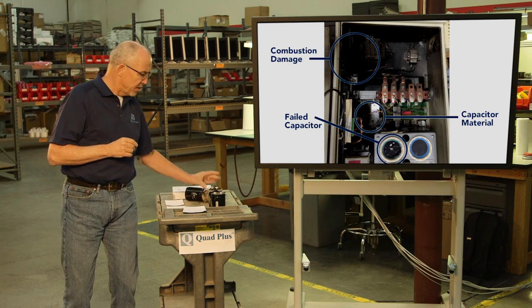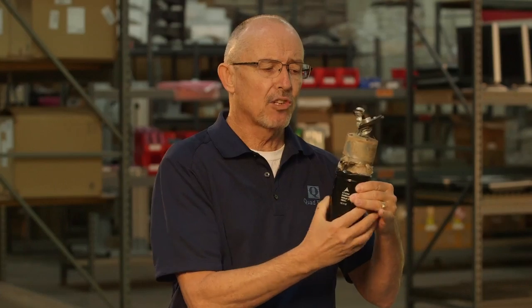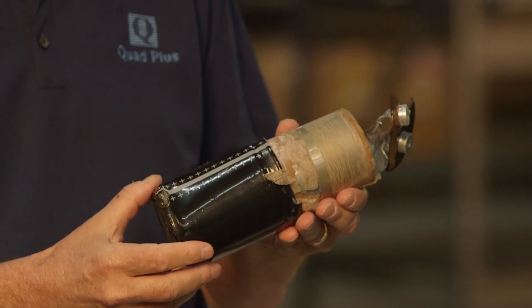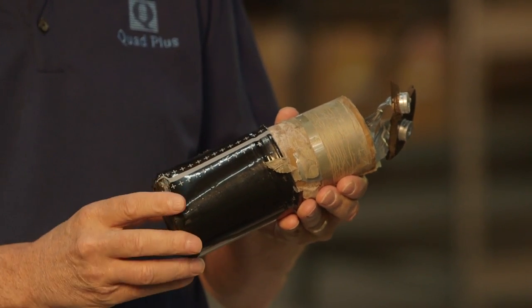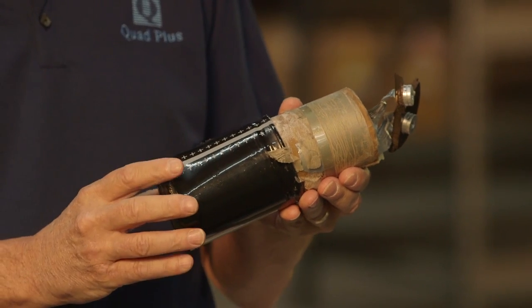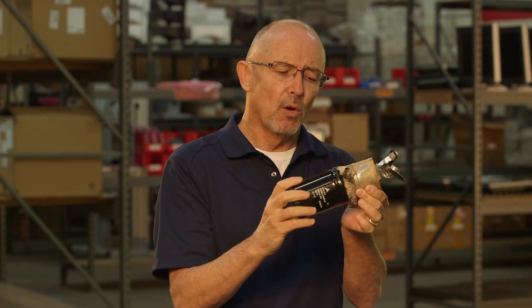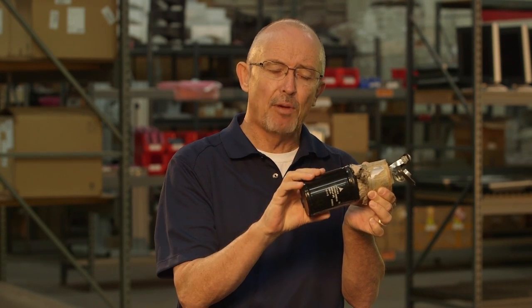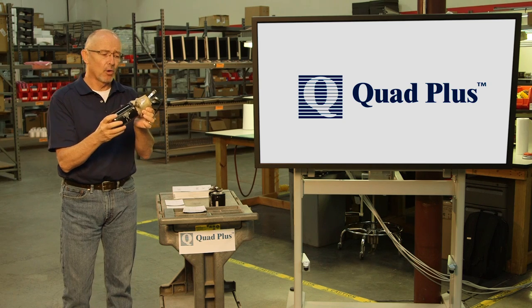This next failure occurred roughly 24 hours after the capacitor was installed. You can see that the foil has actually started to eject from the case, or more accurately the case was being blown off. Not only do you have personnel safety issues in this case, but you also have the potential of this cap falling down through the drive and creating even more collateral damage.